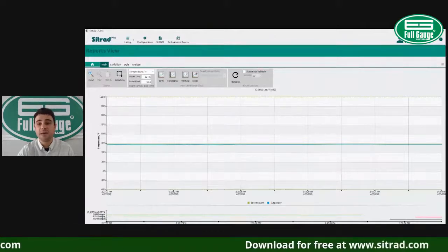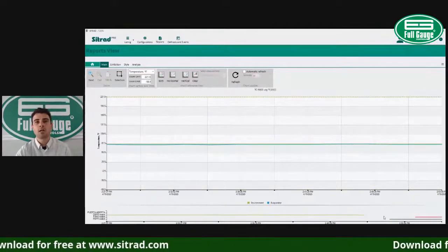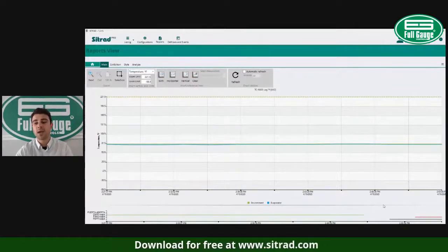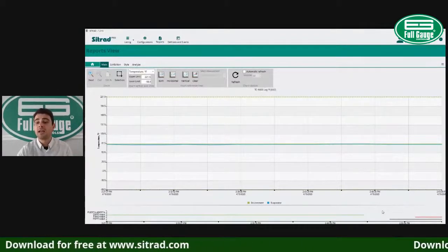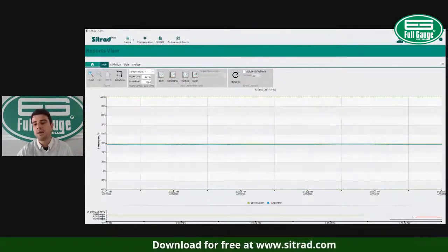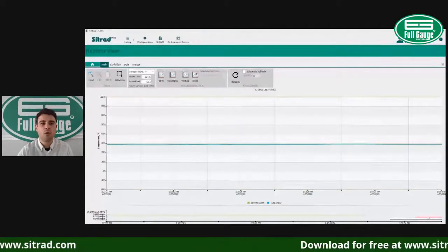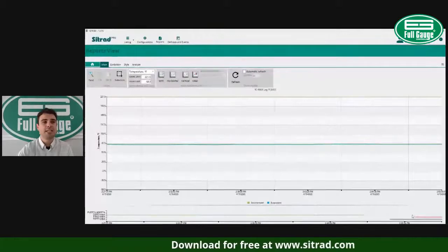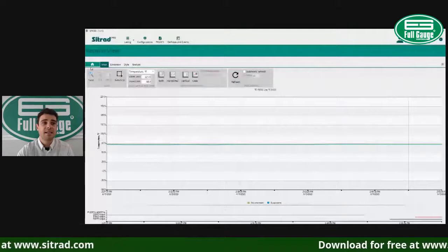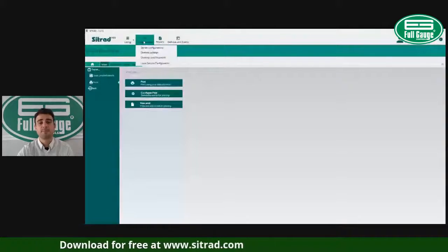That's the draining time. That's the time we let the system drain, so that the water that came from the defrost cycle doesn't freeze up and ice up the coil again. And the fan delay cycle, when the fan was off and the compressor was on. And after the fan delay, we have our normal operation with the compressor on and the fan on. So by taking those reports, you can easily analyze the system data and easily identify potential improvements.